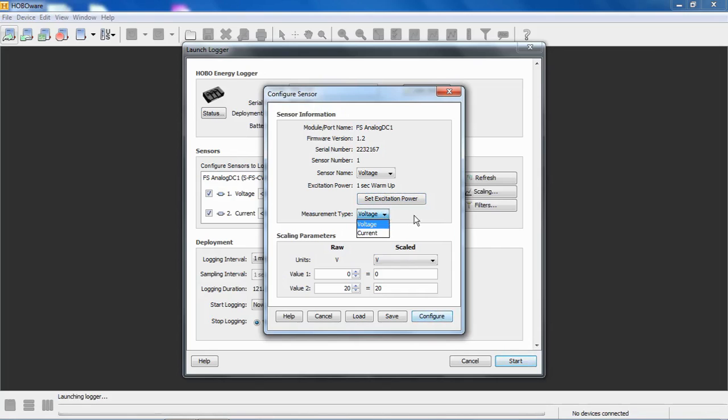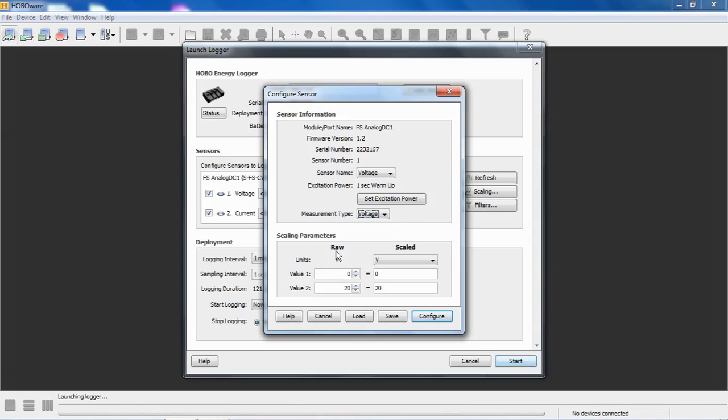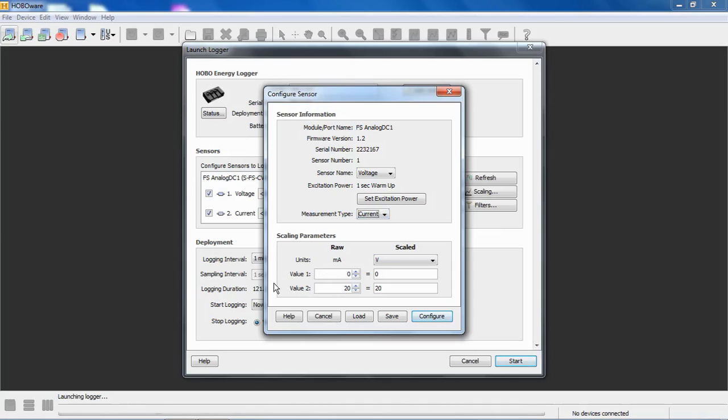Below this is, we need to select what type of measurement we're going to be making. The CVIA, by definition, current voltage input adapter, can take a voltage input up to 20 volts DC or a current input of 0 to 20 milliamps or 4 to 20 milliamps. So with voltage selected, we see that our raw input, so value 1 is 0%, value 2 is 100%. We see that our units is voltage. If we selected current, this would change to milliamps, and this is where we can put in 0 to 20 milliamps or 4 to 20 milliamps, depending on what kind of sensor we're using.